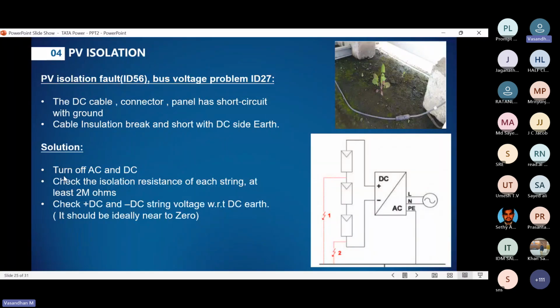Well, how to do it: turn off the AC and DC switch, ACDB and DCDB both we need to switch off. Then check the isolation resistance of each string. Each string we need to check. At least we need to get the ohms range, a resistance value of 2 mega ohms, with the multimeter.